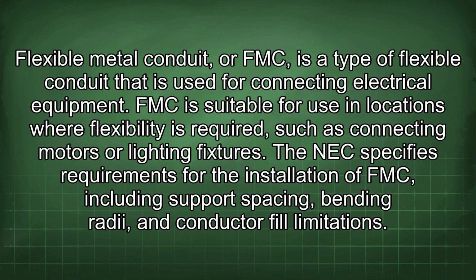Flexible metal conduit, or FMC, is a type of flexible conduit that is used for connecting electrical equipment. FMC is suitable for use in locations where flexibility is required, such as connecting motors or lighting fixtures. The NEC specifies requirements for the installation of FMC, including support spacing, bending radii, and conductor fill limitations.